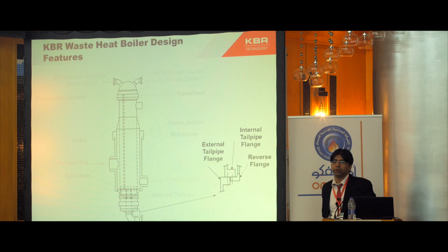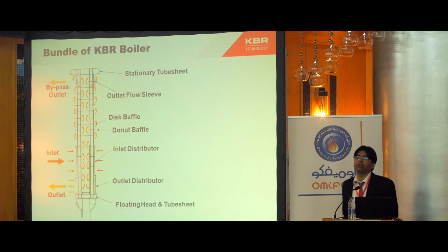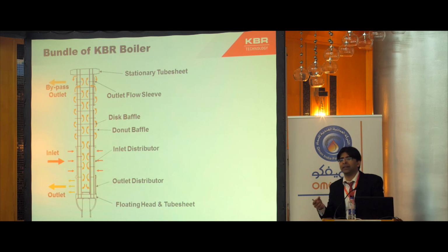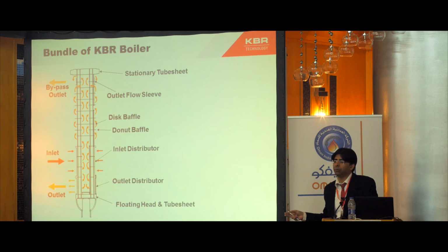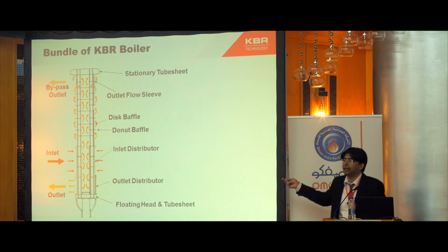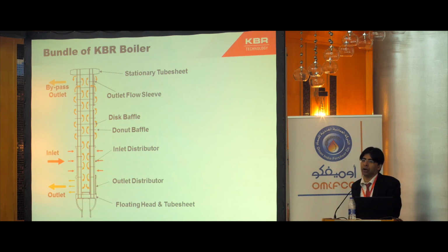So you're keeping the water jacket around? Water jacket around. And you remove the shroud, the metal shroud? Yes. Only the dual layer refractory instead of the metal liner. In some places with this MWK Bayonet design, we have replaced the metal liner with dual layer refractory as well. This is an in-between solution between complete replacement of the boiler with the new floating head design and using the existing bayonet design only with refractory.